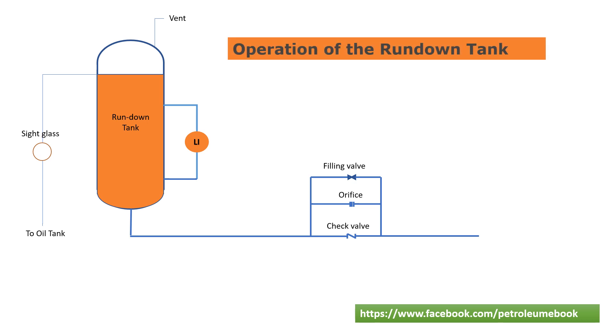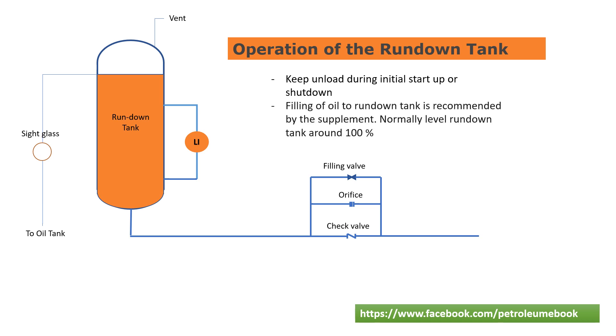The operation procedure for the run-down tank is as follows. The run-down tank is kept unloaded during the initial start-up stage, and the same philosophy is followed for the shutdown stage. The level of oil inside the run-down tank is the parameter on which the rotating equipment start procedure depends. Filling of oil to the run-down tank is provided by a supplemental or additional pump.